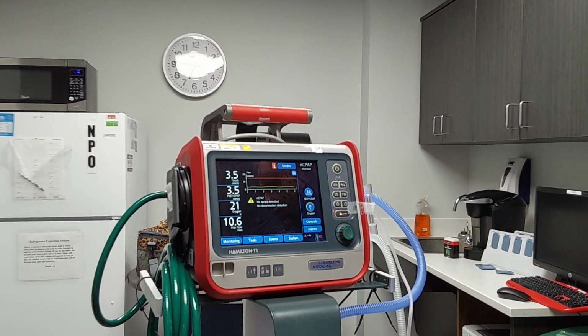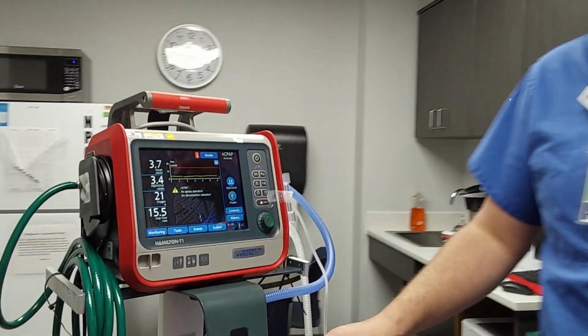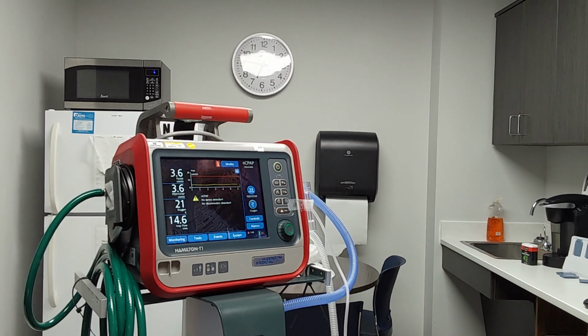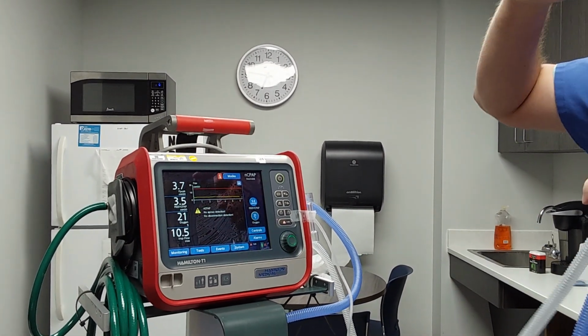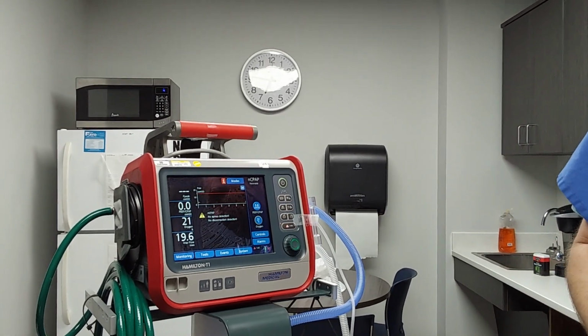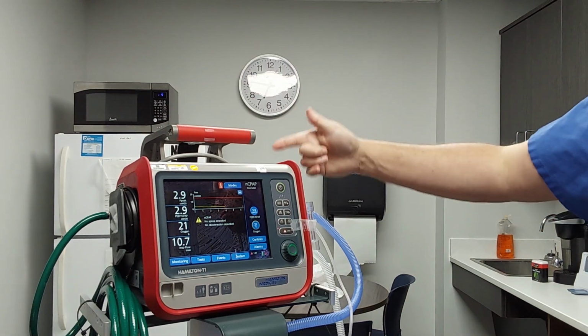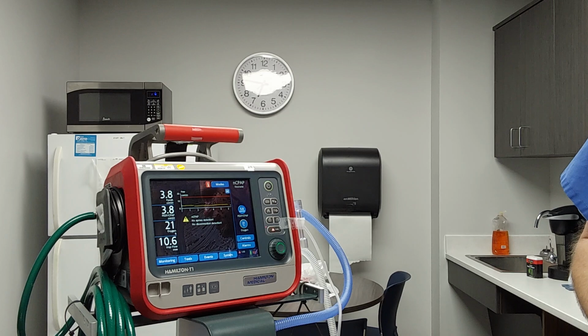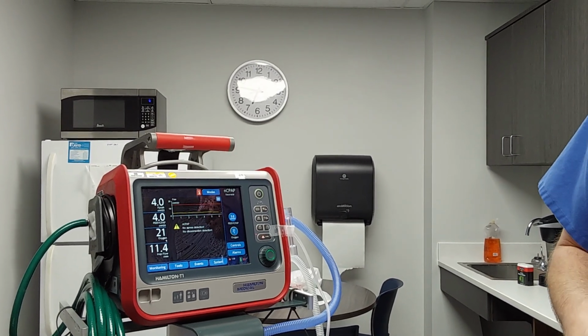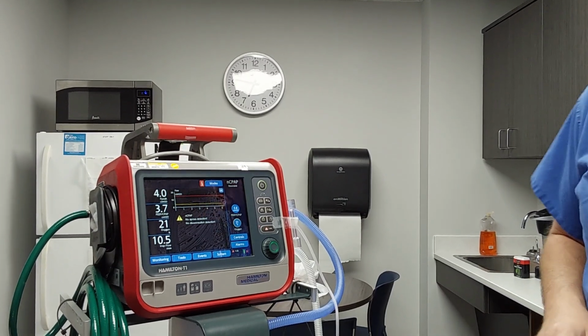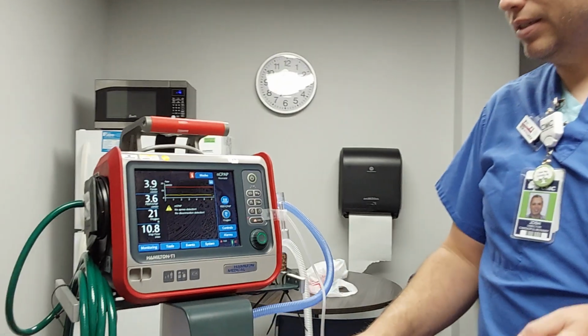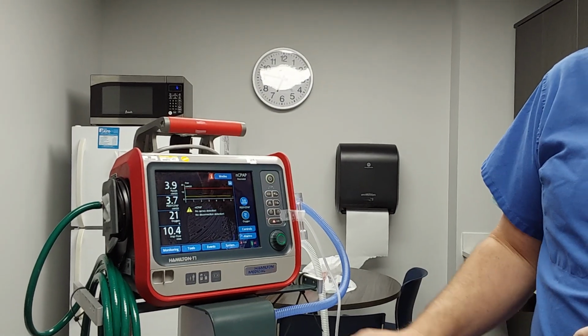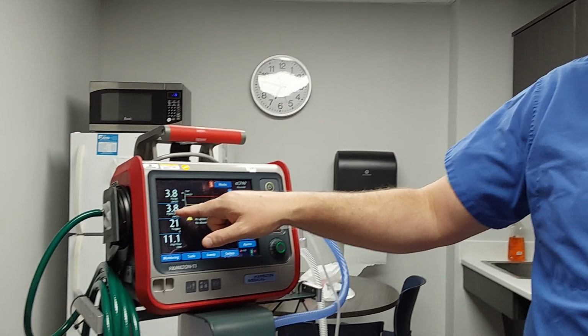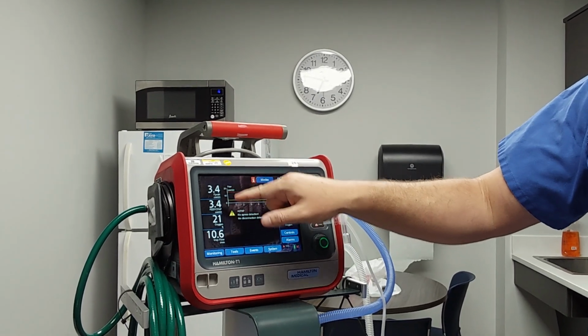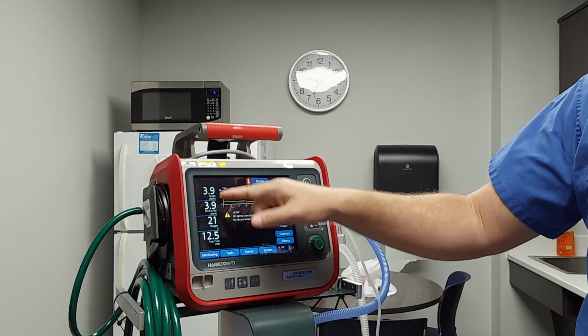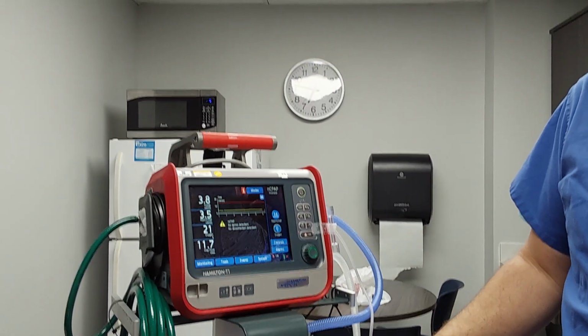So using your RAM cannula, remember you're going to lose about 1 cm of pressure to resistance, just because of how long that RAM is. So remember, even though you're set at 5, only about 4 is actually reaching your neo because of the resistance. So would you want to set it higher than that? I would base it off what your patient looks like. If he's still having retractions, or if you have the wrong size cannula, then you're going to notice this pressure is not going to be able to maintain. Every time that baby takes a breath in, this is going to drop really low, and then you may get some alarms there.